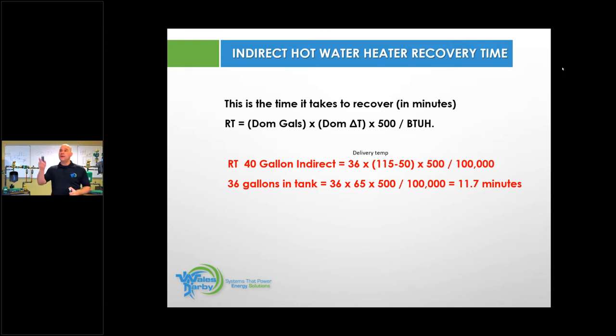Okay? In the first set of parentheses there, 115, that is our delivery temperature to the home. We have a 50-degree incoming temperature. There's our 500. And this is a 100,000 BTU boiler. So in this scenario, we're going to do the math in the parentheses first. So we have a 36-gallon tank, 115 minus 50 equals 65. So it's 36 times 65 times 500 divided by our boiler size. So if I just put a brand new boiler in and everything was piped and pumped properly, and I turn the switch on, in that application, 11.7 minutes after I turn the switch on, the boiler will heat up.